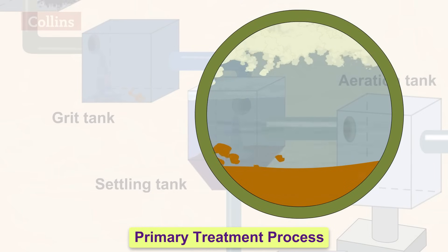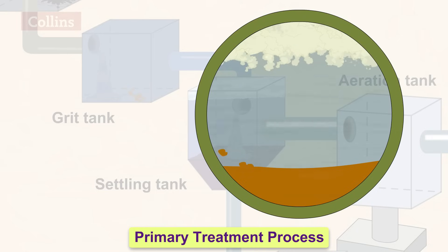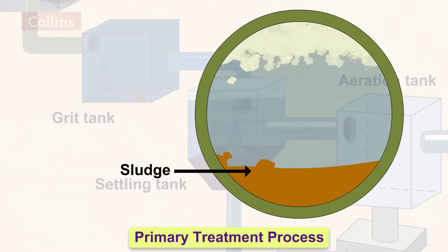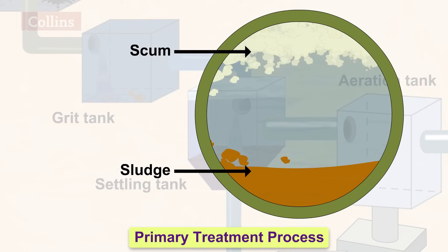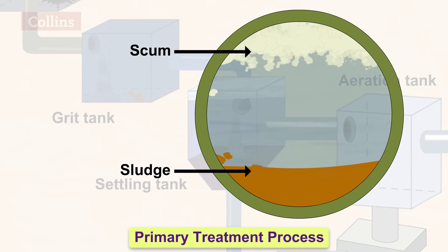Wastes such as soaps, oils and grease rise to the top of the wastewater. The waste material that settles down at the bottom is called the sludge and the floatable material is called the scum. Scum is then removed using a skimmer and sludge is removed with a scraper every few days. The water that is left out is called the clarified water.